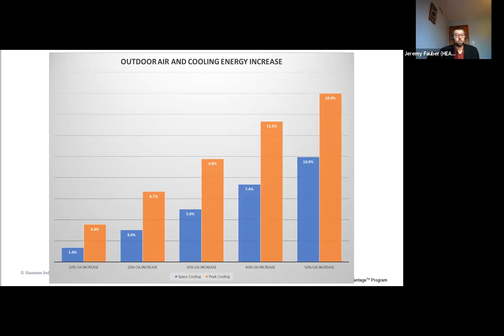So this slide here deals with cooling increases only. This is looking at your cooling equipment. There will be other electricity items that change with this in terms of fan power, but that's not included. This is just looking at your cooling energy usage. The blue bars represent the cumulative increase in cooling energy compared to normal operation. And so for every hour that you've got this 10% outside air above what that normal would be, basically above, say, 75 degrees, because the building that we modeled had an air side economizer. So it was already going to be 100% outside air up until about 75 degrees.